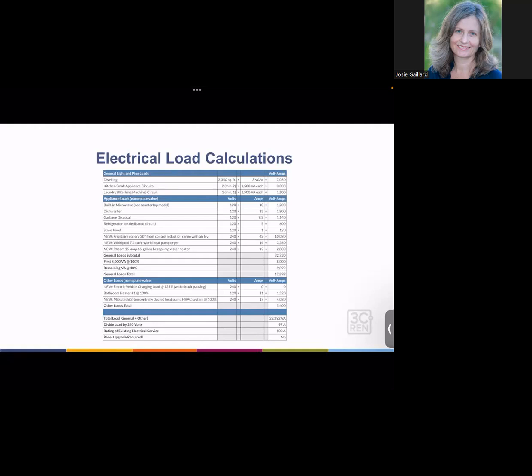Similarly, let's take a water heater. It's going to be on for sure, at different periods of the day, maybe for several hours, but it may not be running at that max current draw. On the other hand, the code is assuming that the HVAC system providing cooling or heating for the home could be running for very long periods of time, and so it could be running at a high level, let's say on a very cold day. So it's more likely to be running during a time when all the other devices in the home are running, and at a higher amperage level. Some devices that have motors come on, and when the motor is just kicking in, the amperage is quite high, current draw is high, and then the current needs reduce once the motor is running and just continuing its operation.